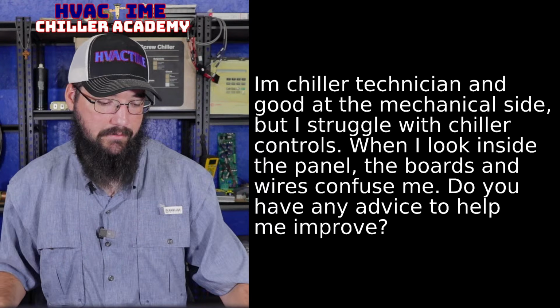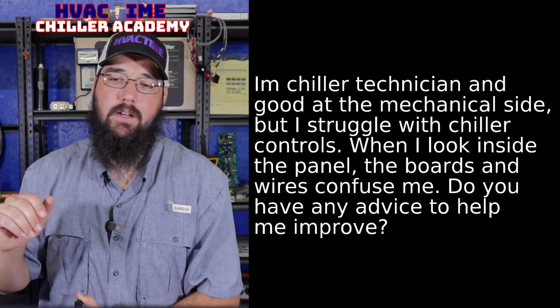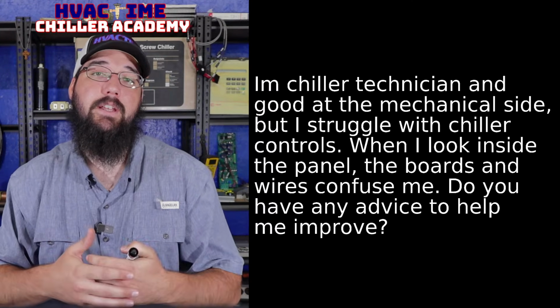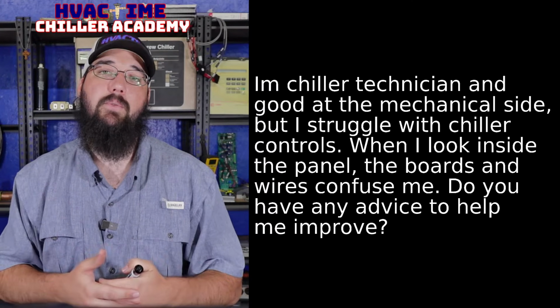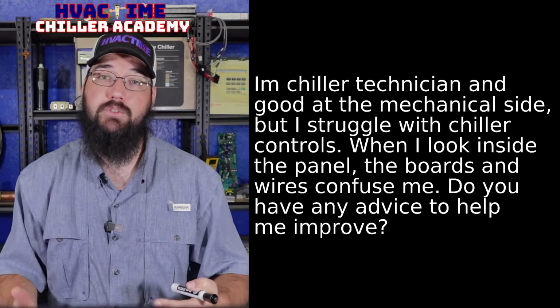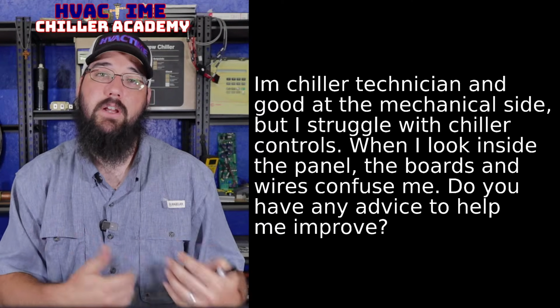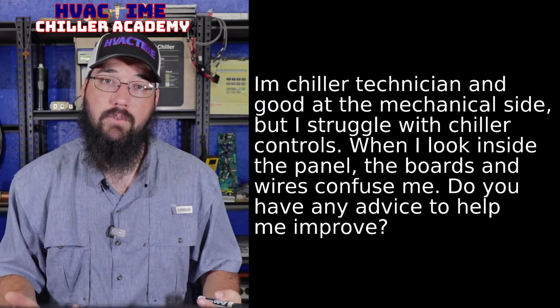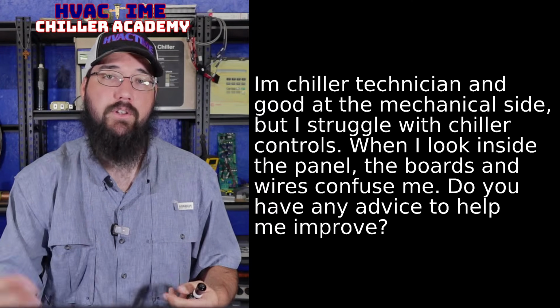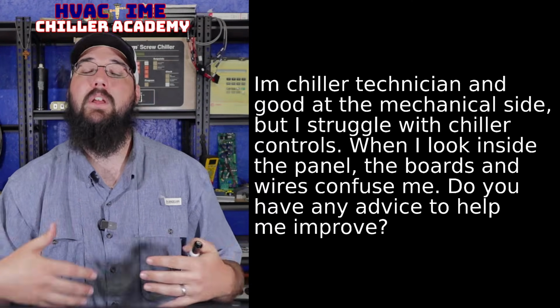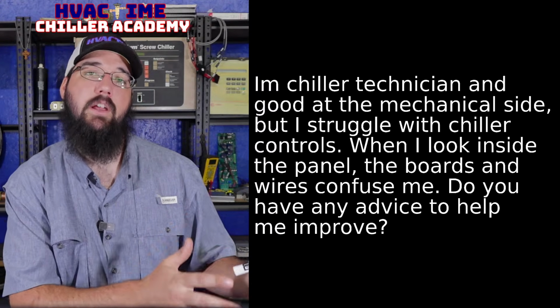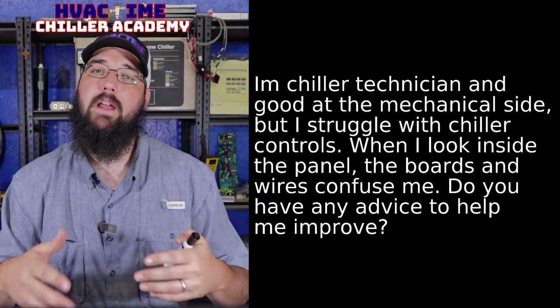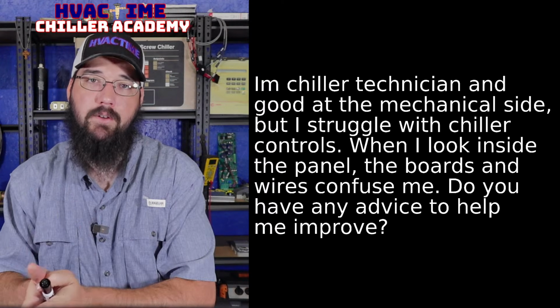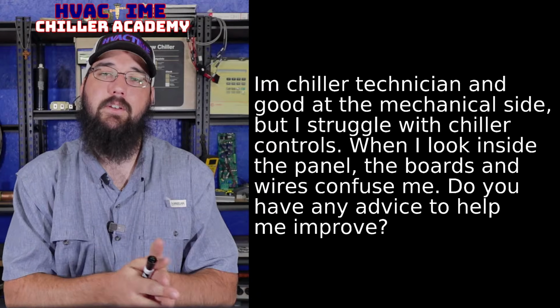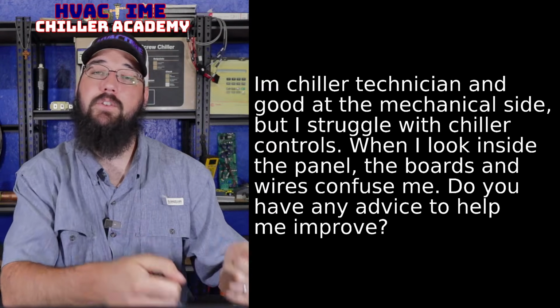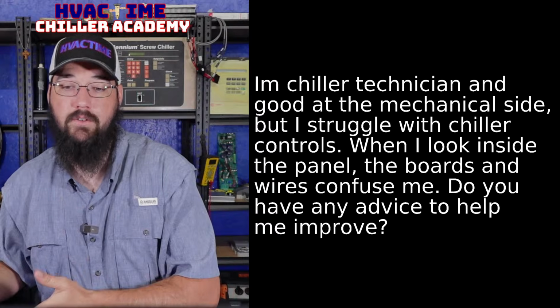That's a whole side trail I'm not going to get into right now. But in addition to that, understand grounded circuits and what a grounded circuit is. When you're troubleshooting, if you have a grounded circuit and you're trying to find a short, you have to disconnect your grounds in order to fully troubleshoot that panel out. So you could find everything on the schematic just fine and be working through it, but if you don't understand a grounded control circuit versus non-grounded, and that transformer has an internal ground, then you have to completely disconnect from it to then find the grounds.